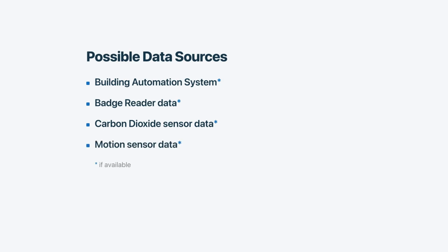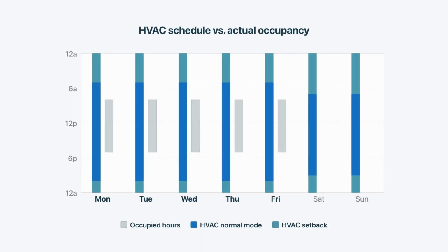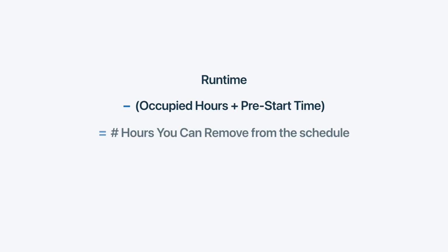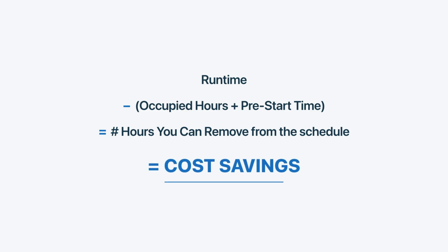And then you're also going to want some zone temperature data so that you can see whether the set point is actually being met during the occupied hours and whether the setback is being hit during unoccupied hours. With those 3 streams of data over a few weeks, the correct schedule for the building is going to become pretty obvious. Not inferred, obvious, based on real data. And again, this comes back to our recurring theme of ground truth. The gap between runtime and actual occupancy plus appropriate pre-start is exactly the number of hours you can remove from the schedule without impacting anybody's comfort, and that will save you money.